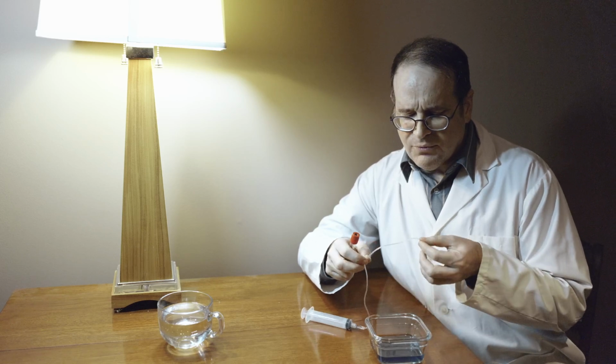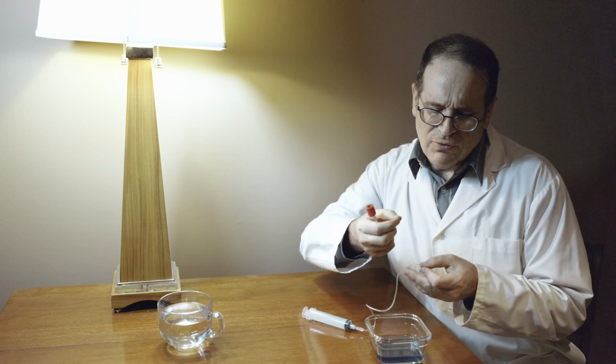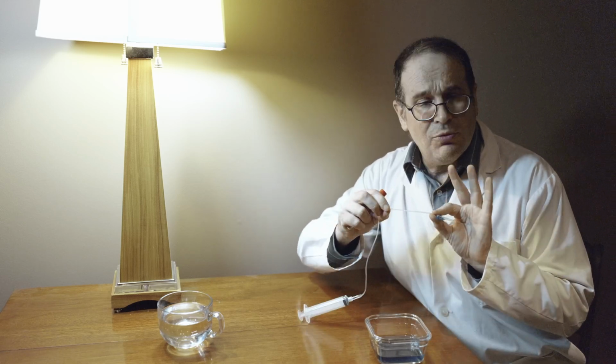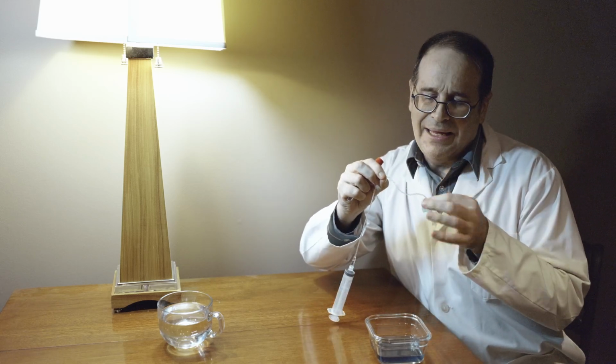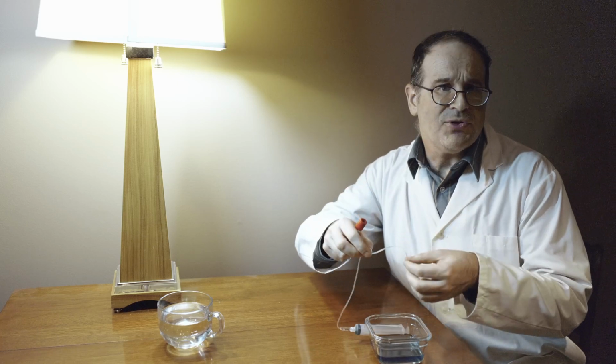We also have the fact that we have a tube which is curved. Whenever you have a curved surface, you're going to have a little bit of a magnification effect. That magnification effect will be minimal at the center and increase as you go towards the more curved and outer portions of the tube. So for the tube of a normal diameter and of this material, and for the bubbles of the size we're seeing, in the mid portion of the tube we can expect about a 12% additional increase in the bubble size simply due to the magnification.